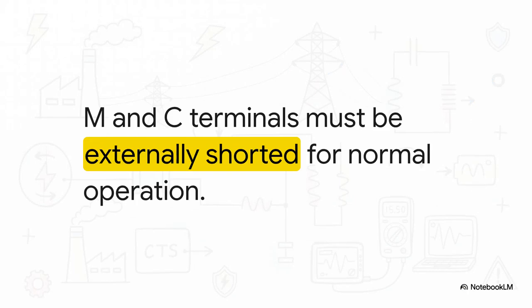This brings us to a really weird design quirk. At first glance, it honestly looks like a manufacturer's mistake, but it's actually an intentional stroke of genius. For almost every practical, everyday setup to measure standard single-phase power, you have to manually bridge the mains and common terminals, M and C, with a physical piece of wire yourself. Without that external bridge, your meter literally does absolutely nothing.